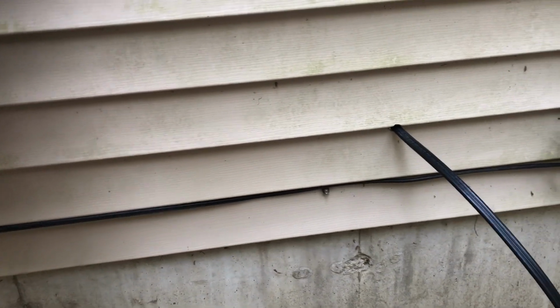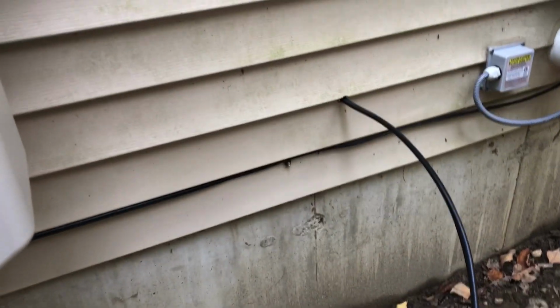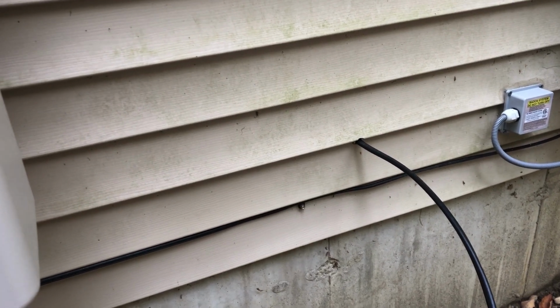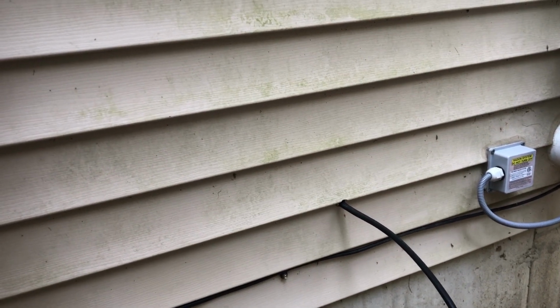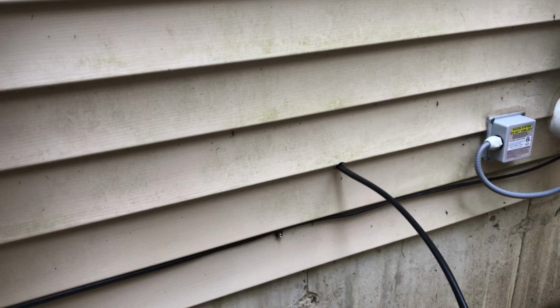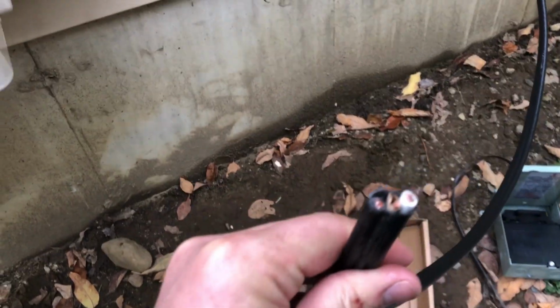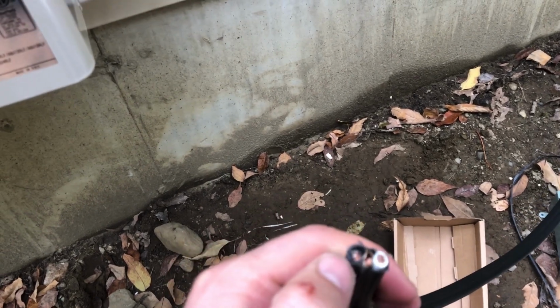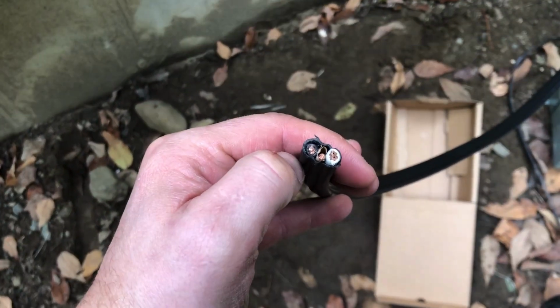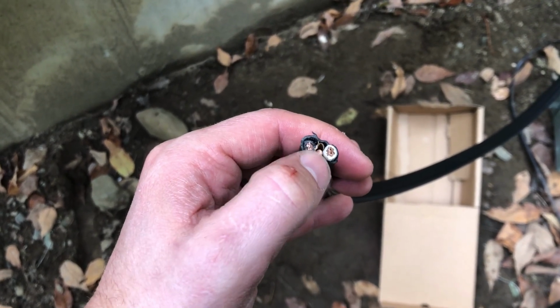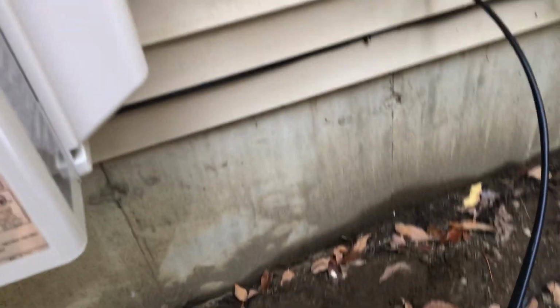So now let's talk about the appropriate wire size. You want to go with a solid copper wire, and what I went with was an 8 gauge wire. If you look up online, there are lots of ampacity charts that tell you what size wire you need. I knew that I needed a 40 amp rated wire, and I knew that I needed to go approximately 40 feet. So by looking at the chart, I knew that I needed an 8 gauge wire. So this is an 8-2 wire. As you can tell, it's got two wires, the black and the white, both of which will carry power, and then it's got a ground. So it has no neutral. Again, this is an 8-2, what you need for a 40 amp draw.